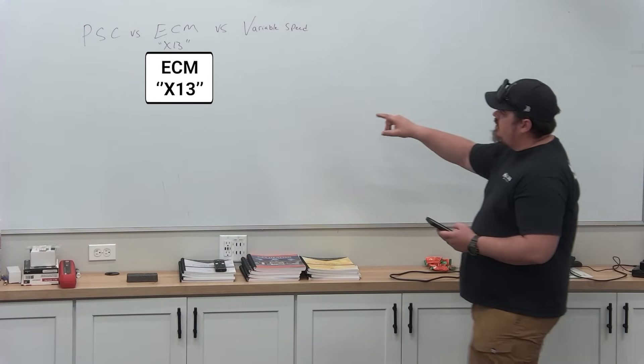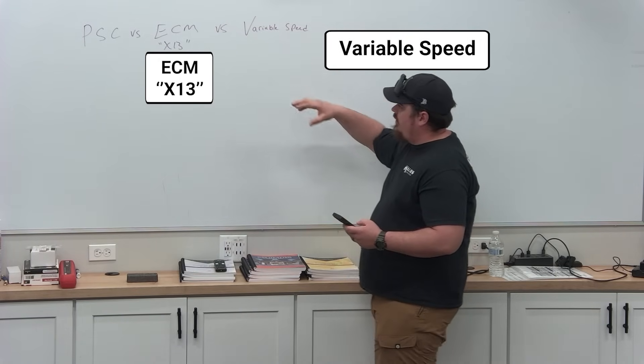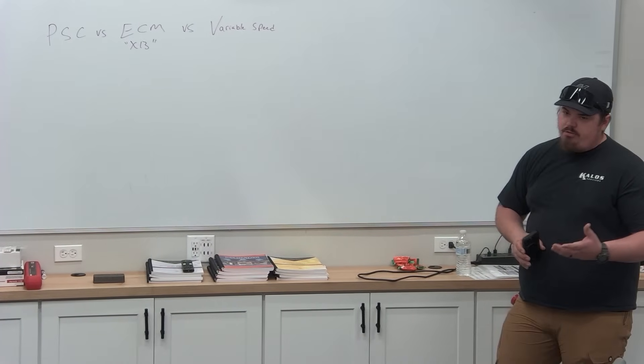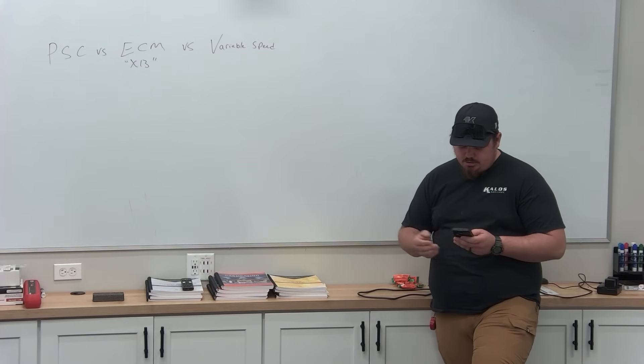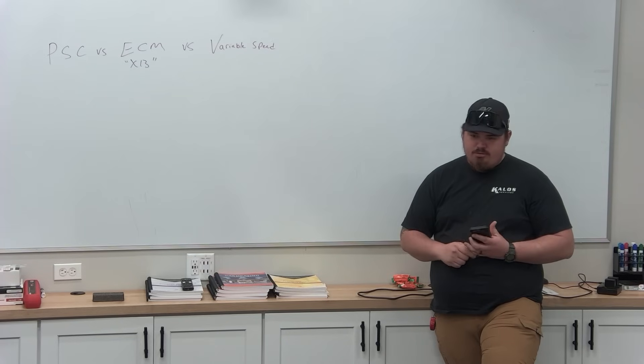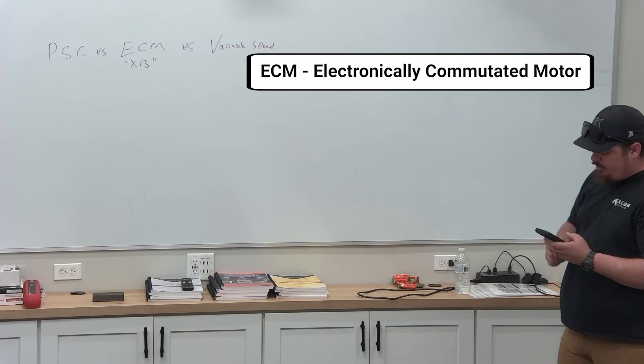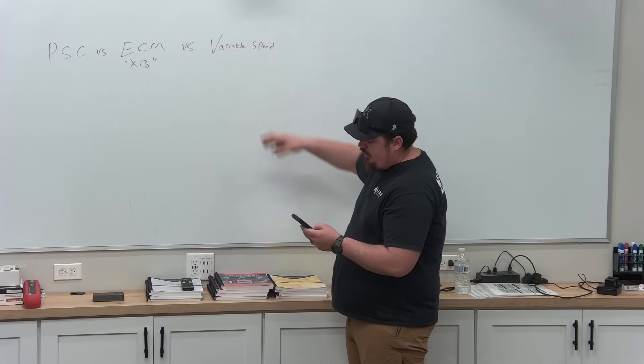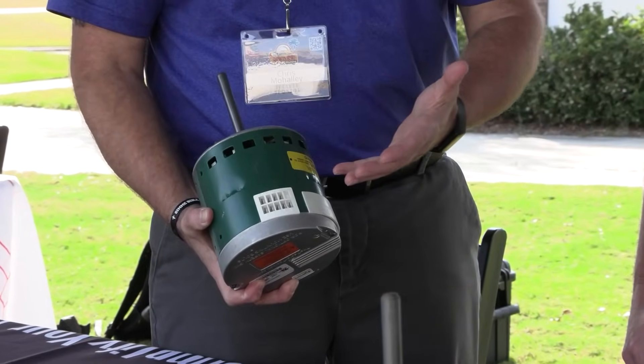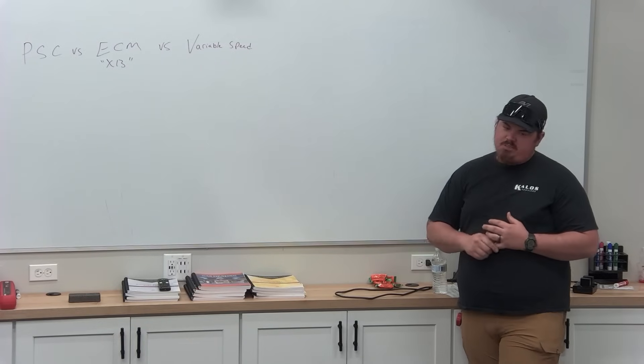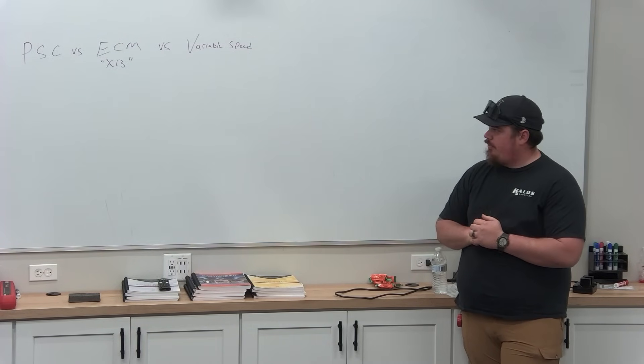ECM motors and variable speed are essentially the same, but they regulate airflow a little differently. The industry standard name for ECM motors has become the X13 — the Genteq motors, the ones we use for all the FJ swap-outs. ECM stands for electronic commutating motor. These motors have internal capacitance built in, and they work off a three-phase system, reversing the plus and minus polarity to actually create blower speed.